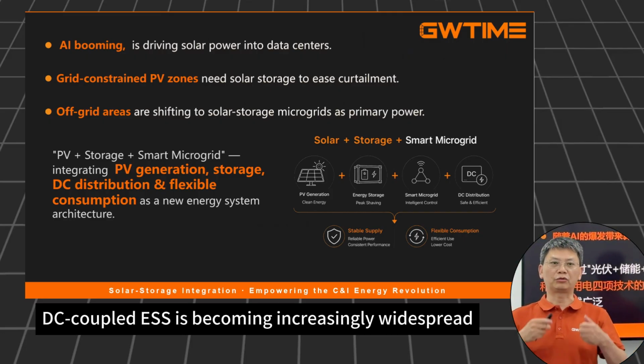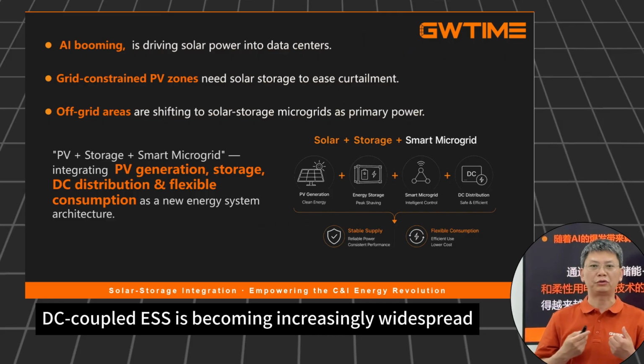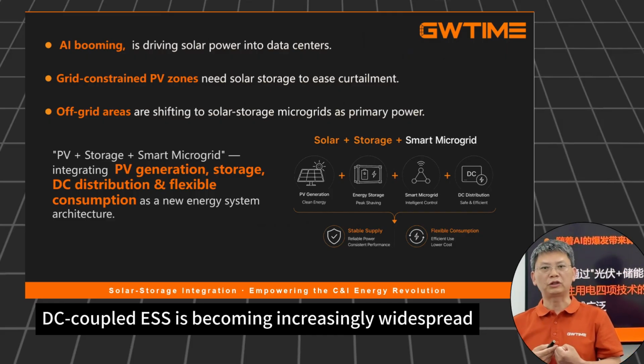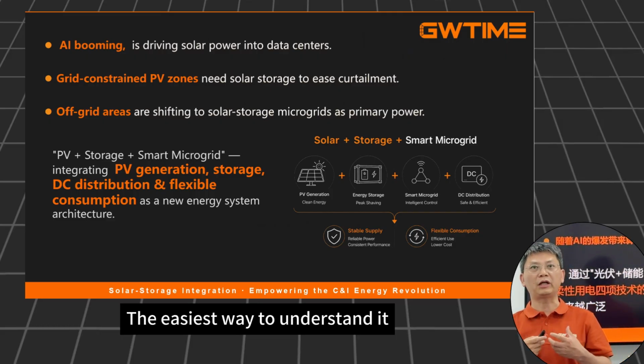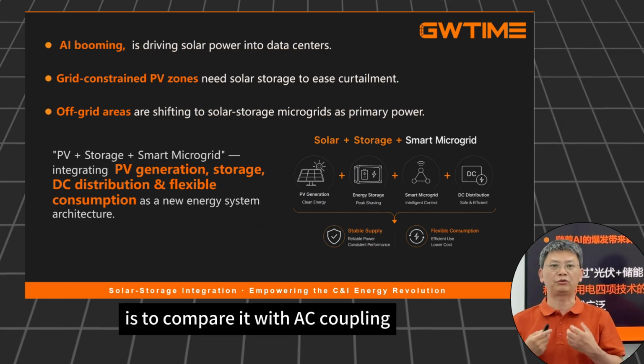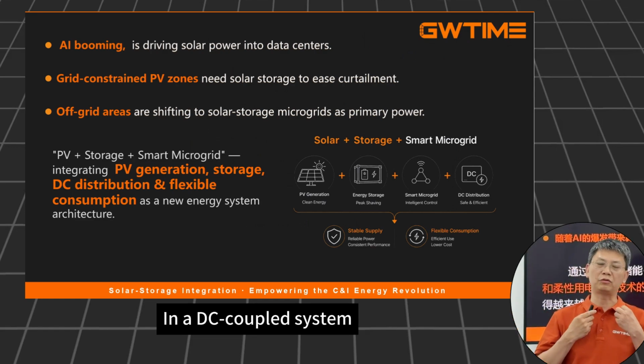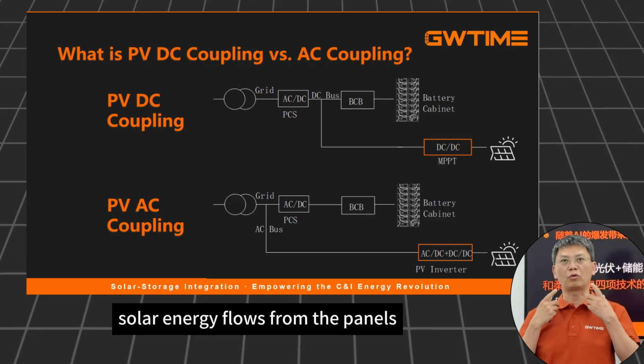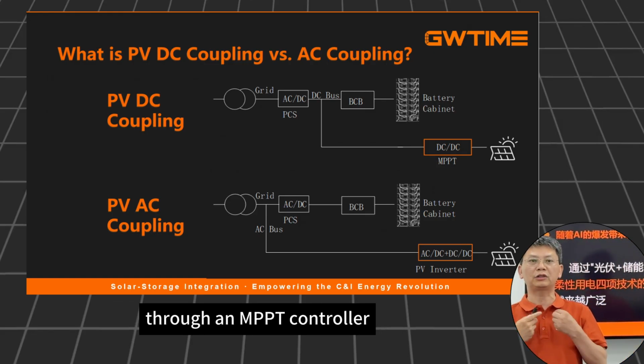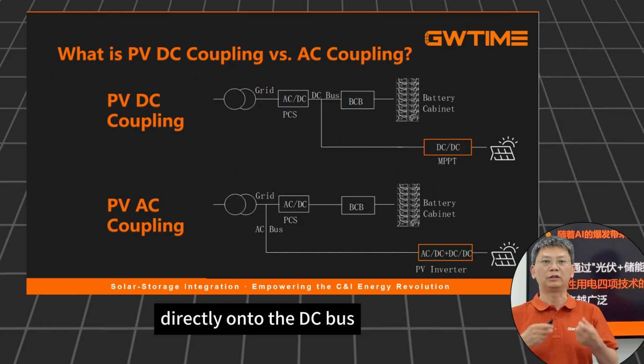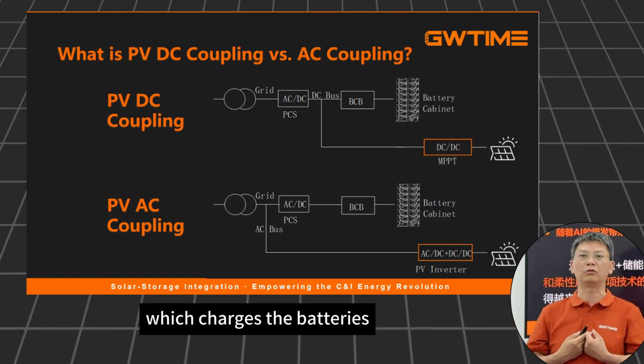In these systems, DC coupled ESS is becoming increasingly widespread. What is DC coupling? The easiest way to understand it is to compare it with AC coupling. In a DC coupled system, solar energy flows from the panels through an MPPT controller directly onto the DC bus, which charges the batteries. That is it.